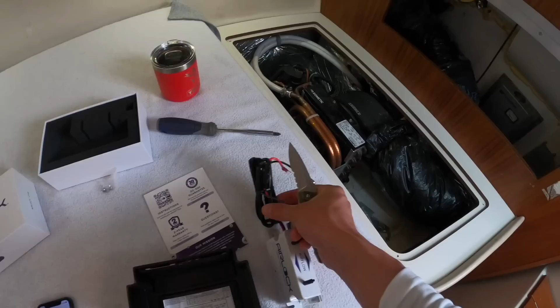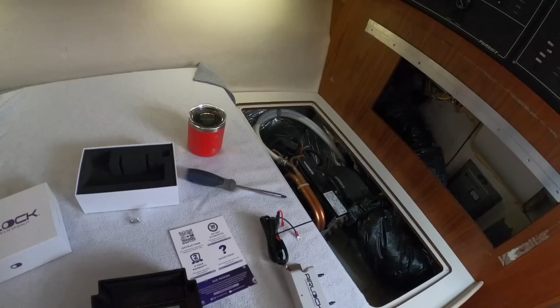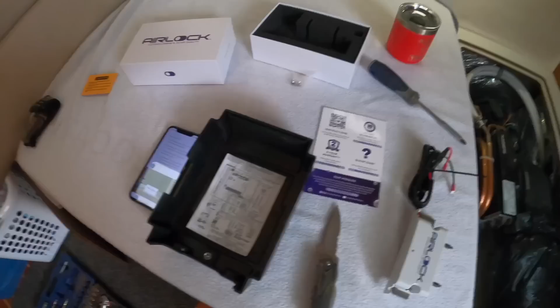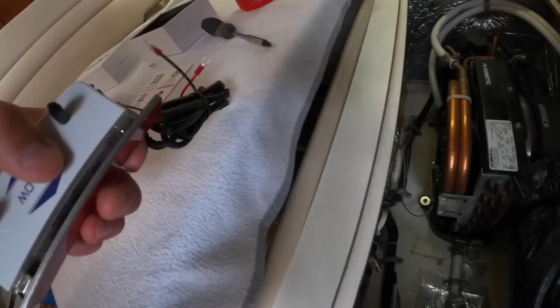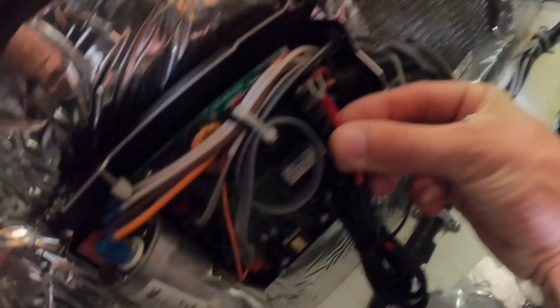Alright, we're going to pop this zip tie off this bad Larry here, so I can get that over to the box. I was just looking through my wiring diagram and double checking, but I believe my red and black—when I have this down here, my red's going to tie into this red here, and my black's going to tie into this black here, and that'll be tied to the blower motor so it kicks on and off.